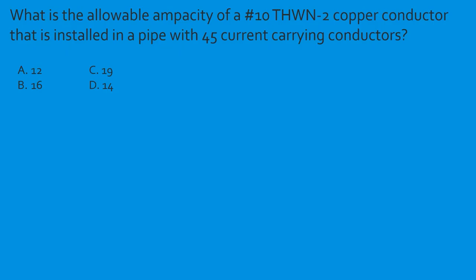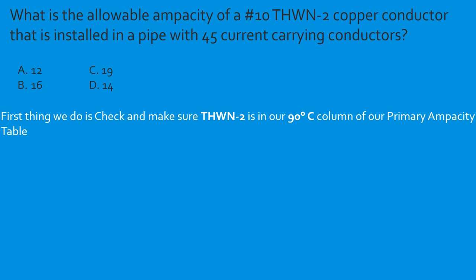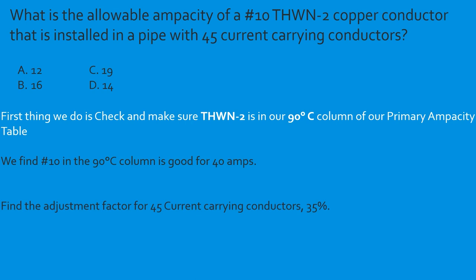Question: What is the allowable ampacity of a number 10 THWN-2 copper conductor installed in a pipe with 45 current-carrying conductors? Confirm insulation is in the 90°C column. Number 10 in the 90°C column is good for 40 amps. Forty-five conductors — adjustment factor from the bundling table is 35%, or 0.35. So: 40 × 0.35 = 14 amps. Select D.